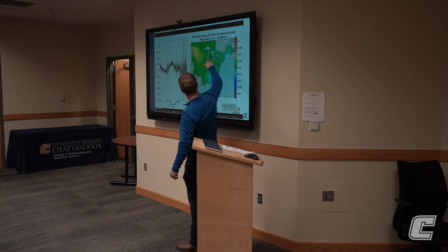So that was what we call a resonance effect. There was a unit here in the Fort Lauderdale, I've already forgot where, I think it was Fort Lauderdale. It's been so long. No, it wasn't. It was Tampa. There was a unit in the Tampa area that was oscillating because it had lost a voltage signal to its controller. And it didn't know how to control the output of the unit. It lost its reference.